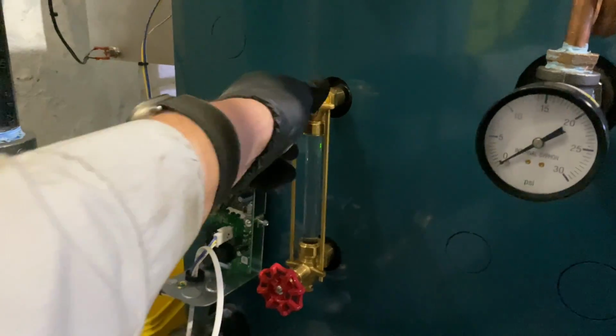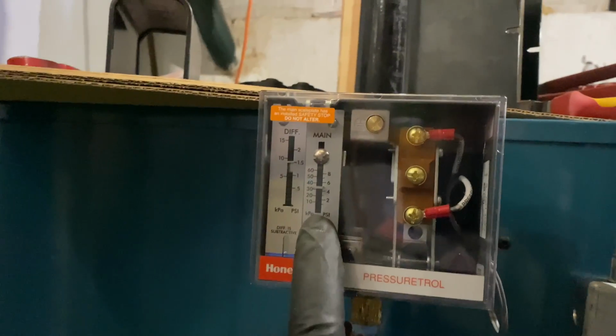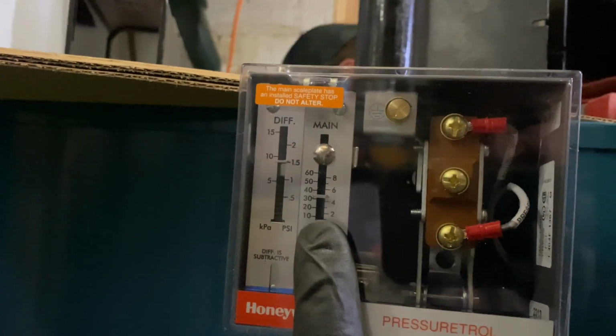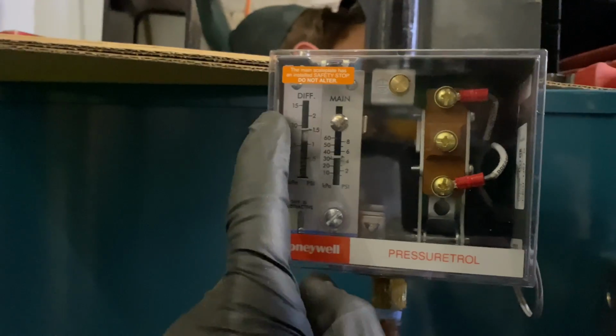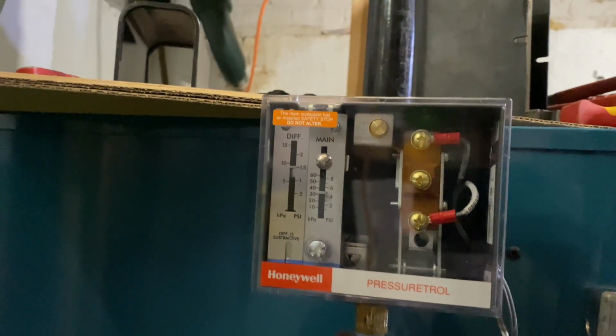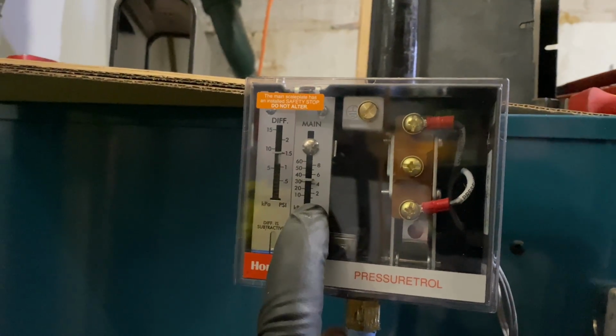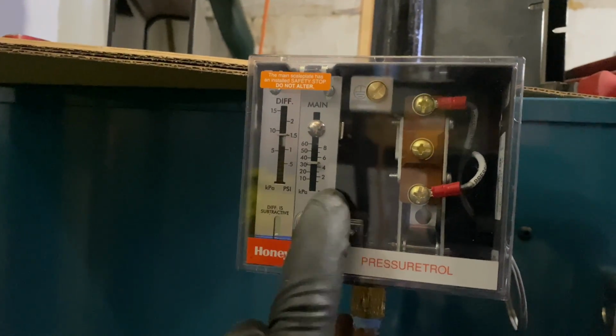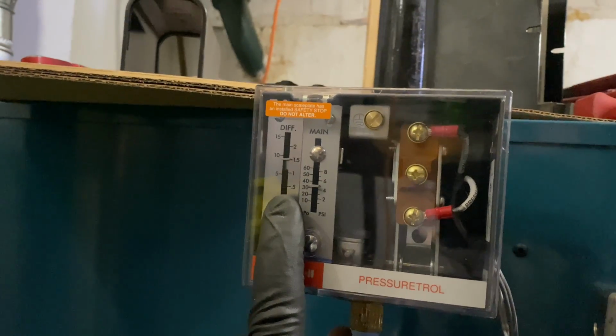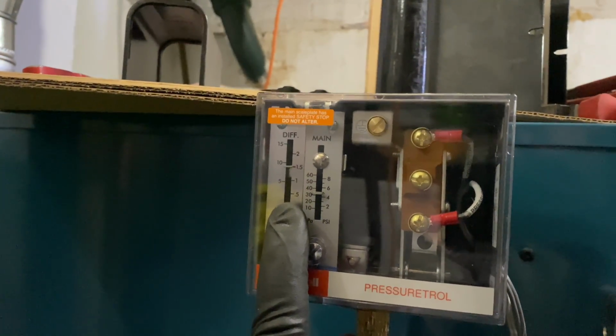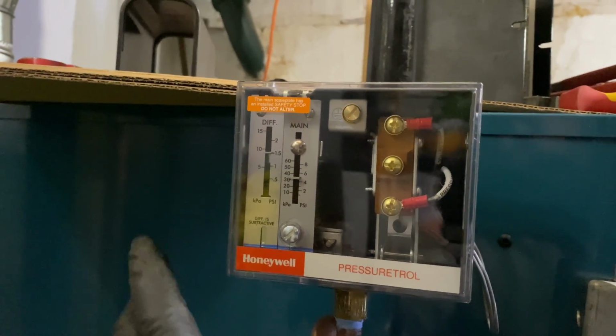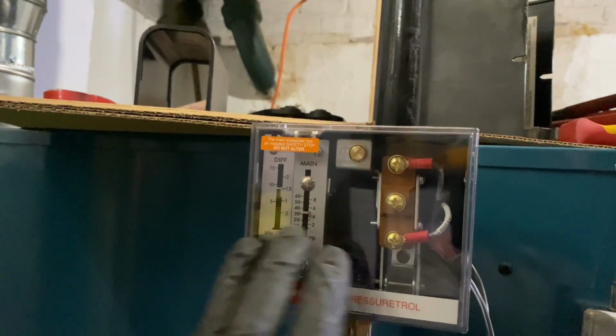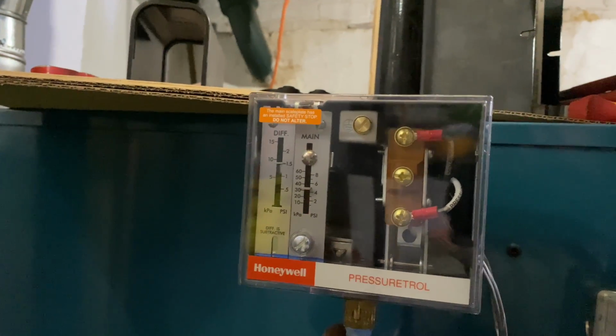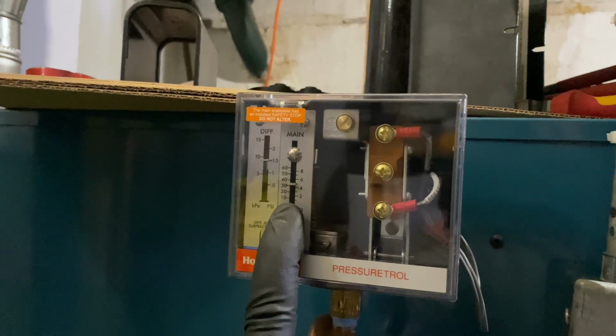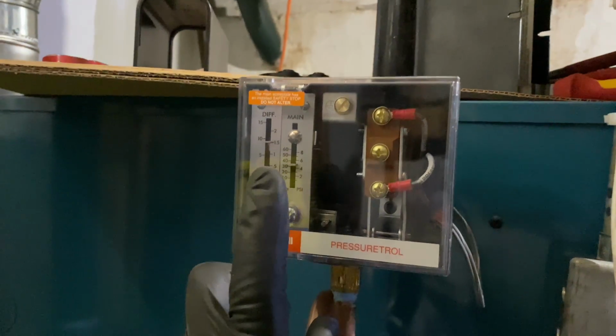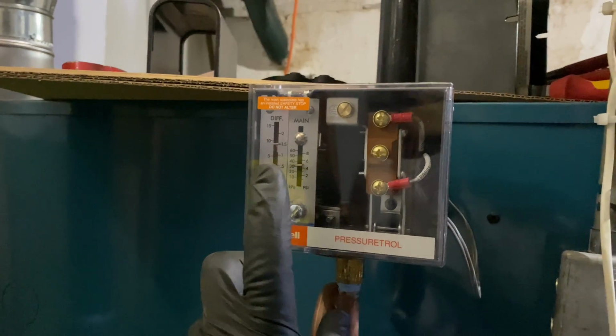One of the things that Dan Holohan likes to talk about is having our Pressuretrol not set at 4.5 psi and a differential of 1.5, but having this main pressure at around 1, which is not even registered on here, and 0.5. But the good old folks at Burnham, US Boiler, say this is where they want it to be. I don't like that, because the higher you make your Pressuretrol, the more fuel you're going to spend to give you the same result.